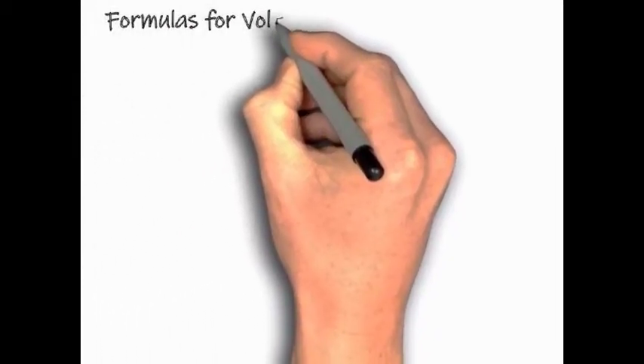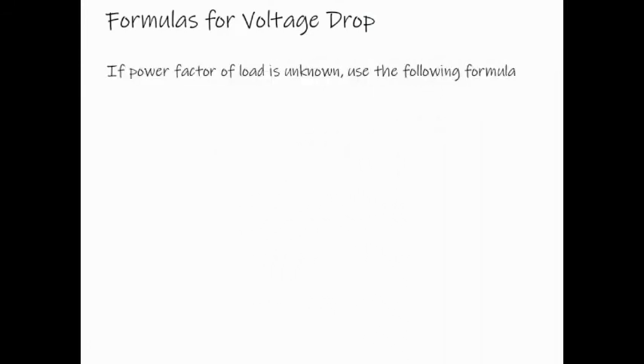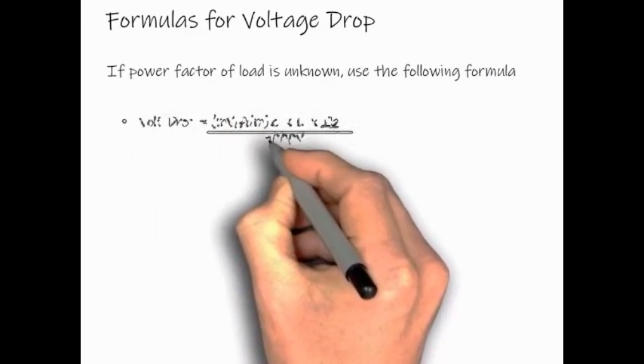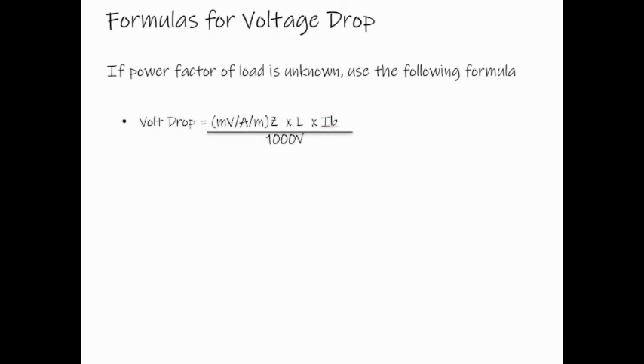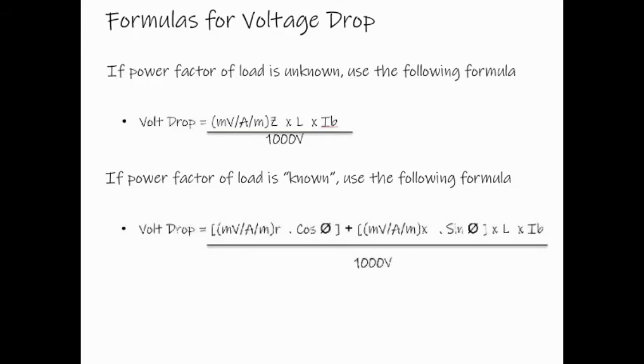To calculate voltage drop, there are two key formulas. If the power factor of the load is unknown, we will use the following formula: Voltage drop equals Z, which is the value of the impedance voltage drop, multiplied by L, multiplied by current in the circuit, and divided by 1000 volts. If the power factor of the load is known, we will use the following: Voltage drop equals R, which is the value of the resistive voltage drop, multiplied by cosine theta, plus X, which is the inductive reactance value, multiplied by sine theta, multiplied by L, that refers to the cables in meters, multiplied by current in the circuit, divided by 1000 volts.